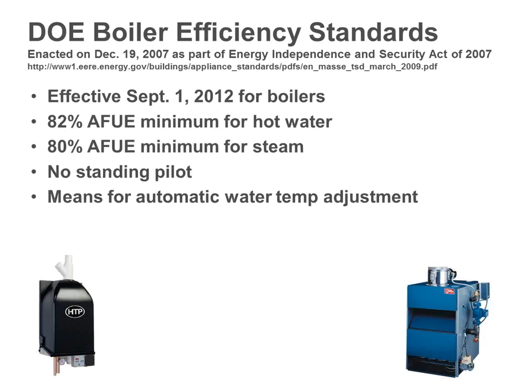The second thing, and probably the biggest reason people are replacing boilers now, is energy costs. We all know the efficiency standards have gone up. Look at the first slide here. In 2012, we had a major improvement. Basically, we went to 82% for hot water and 80% for steam. The two things that you really find out is we got rid of the standing pilot totally, and the government required us to have sort of an automatic water temperature adjustment.